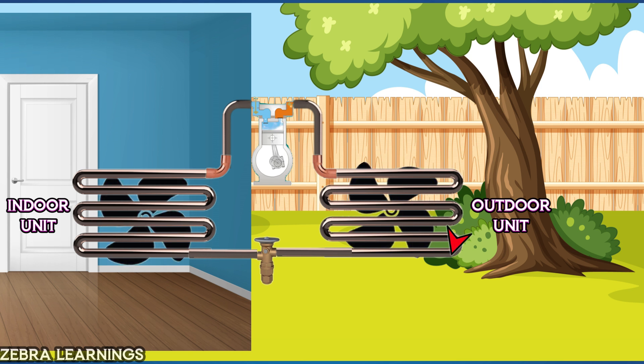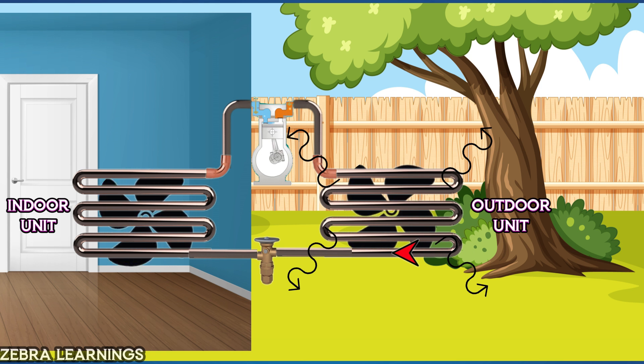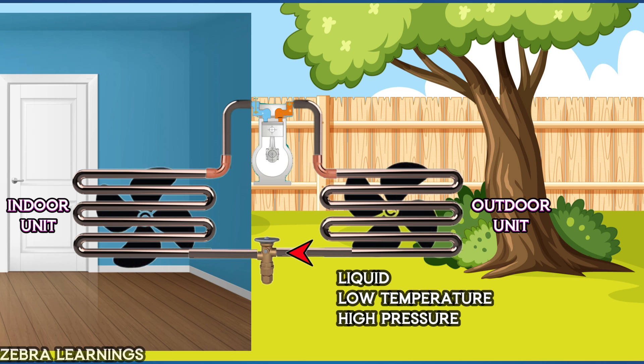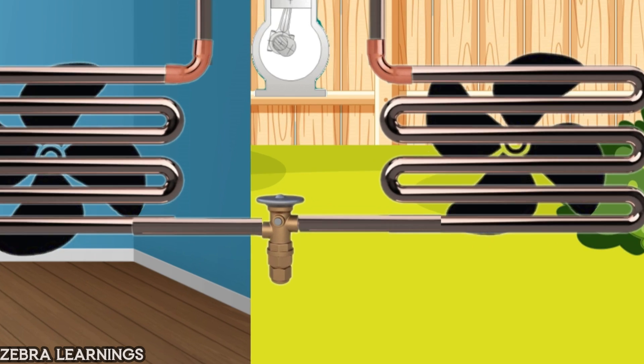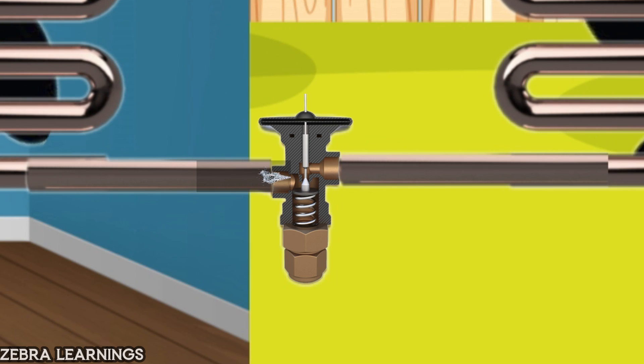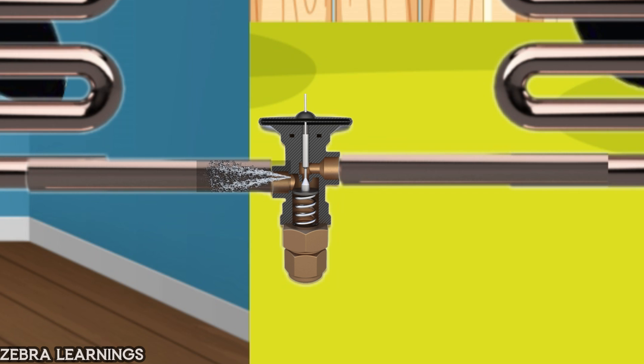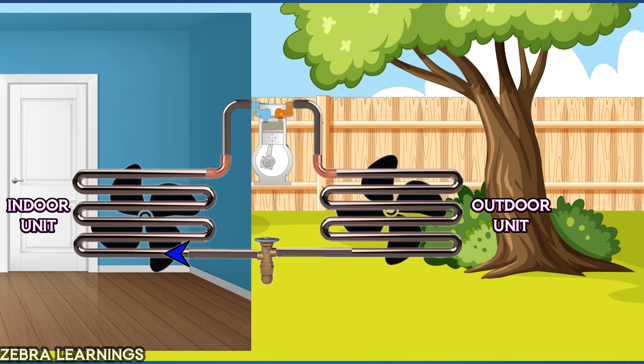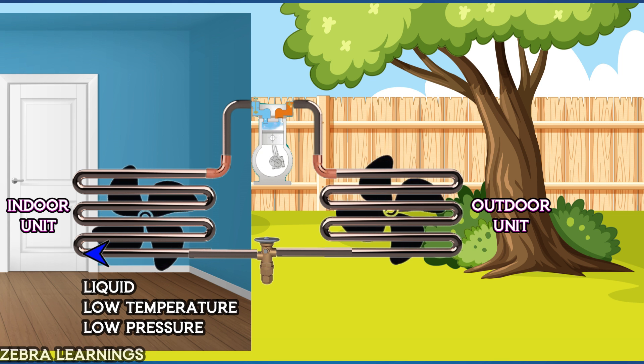The refrigerant then goes to the expansion valve at high pressure and liquid stage. The expansion valve expands the refrigerant and rapidly reduces its pressure. Since the pressure of the refrigerant decreases rapidly, its temperature also decreases, and the refrigerant enters the evaporator at low temperature and low pressure.